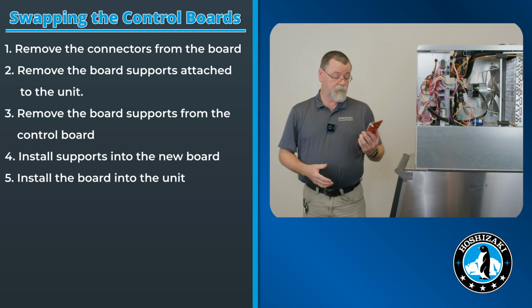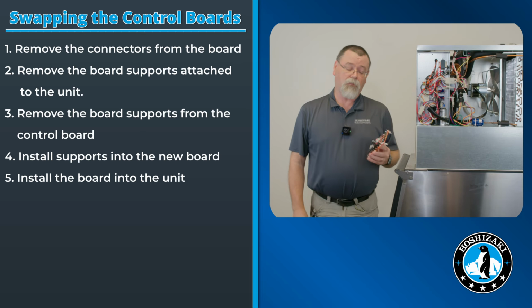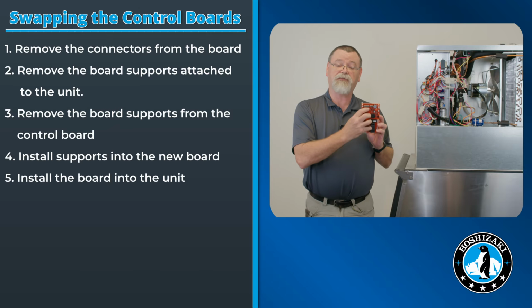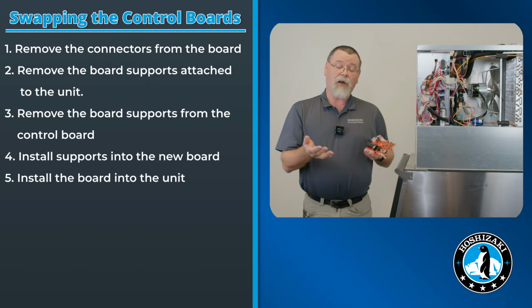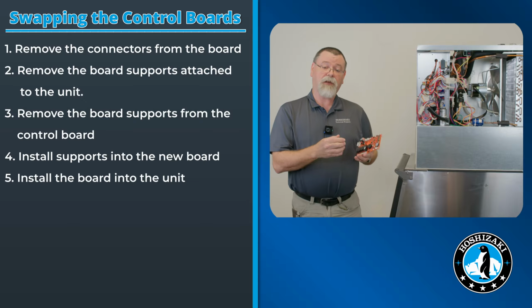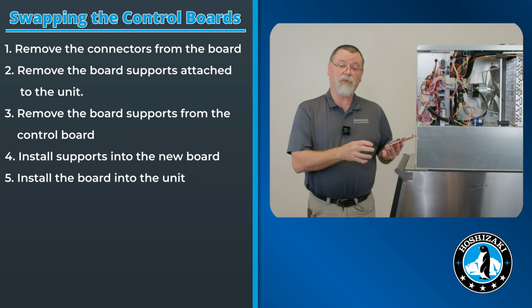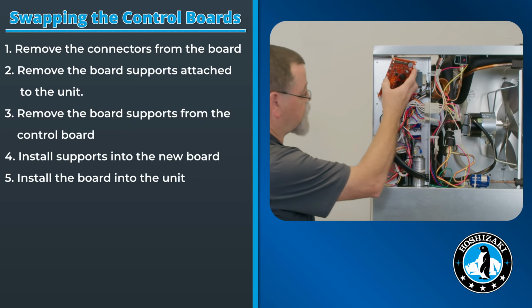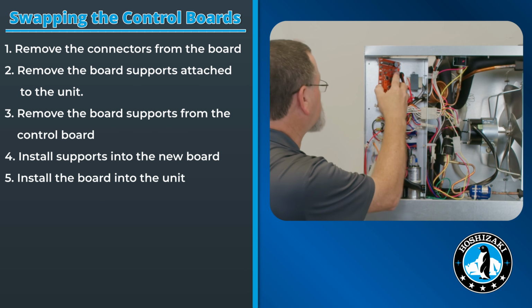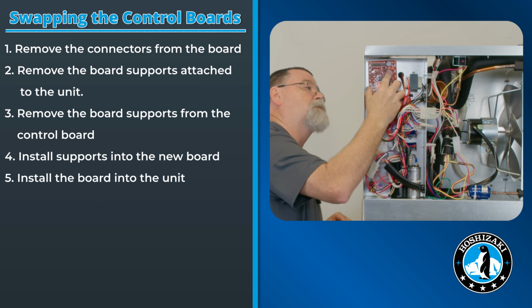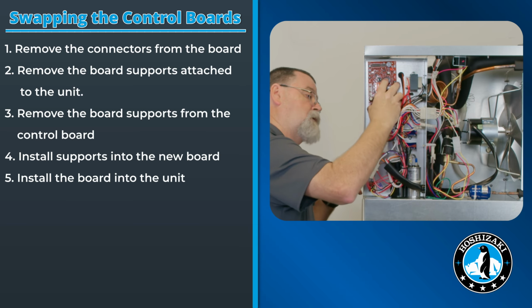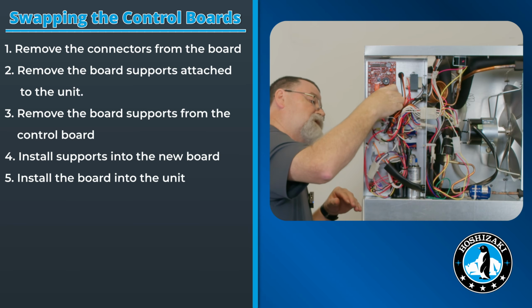Now that we've got the support connectors on the new board, this will be a good time to double check your dip switch settings by your wiring label or the service manual before installing the board into the unit. So you just put the board back in the unit in the same location it was in by lining up the board connectors, pushing in on the board connectors, and making sure it's locked in place.